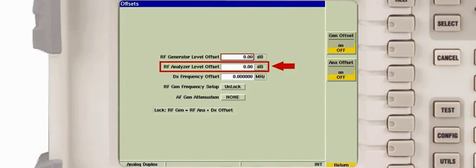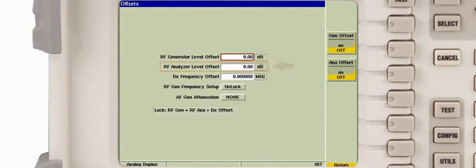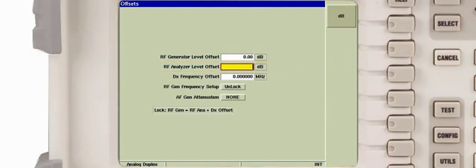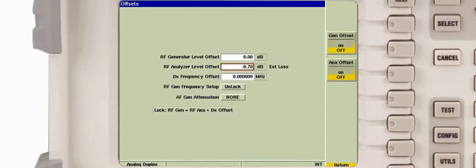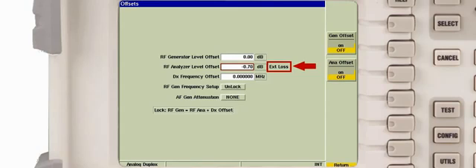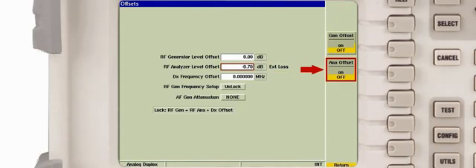The loss value is entered into the RF analyzer level offset field. Note that because the value is negative, the instrument notes the value as an external loss. The analyzer offset soft key is pressed to toggle the offset compensation on.